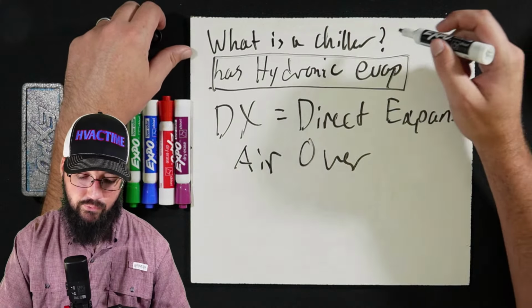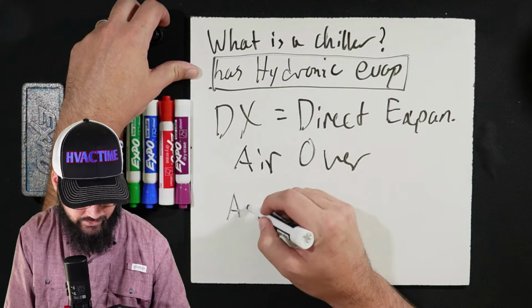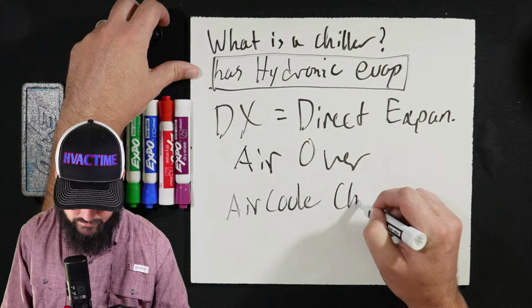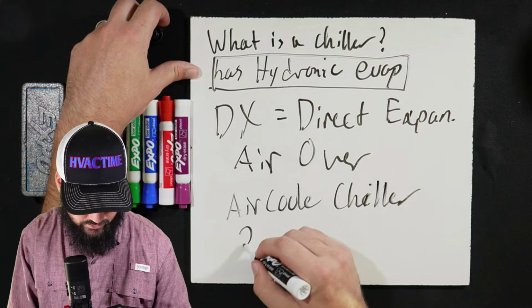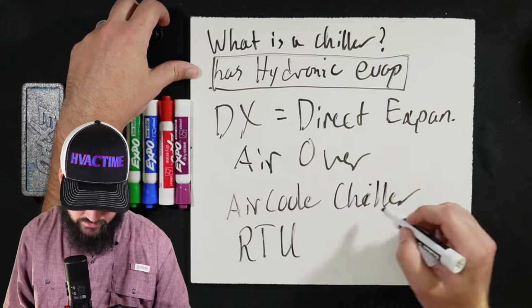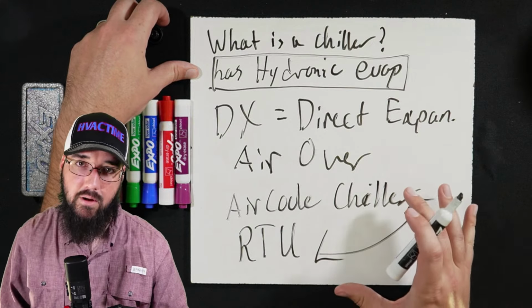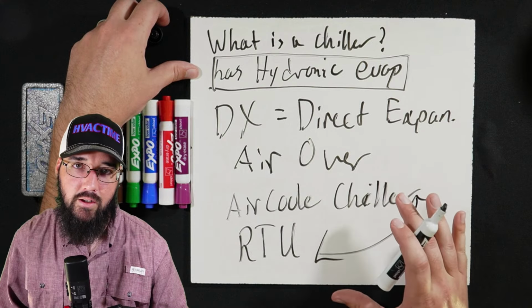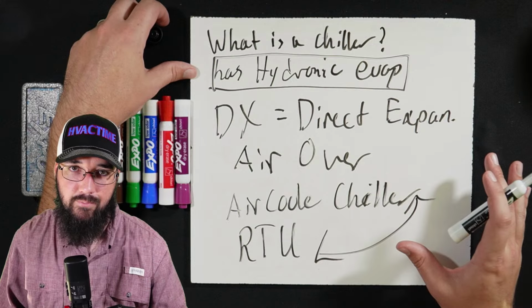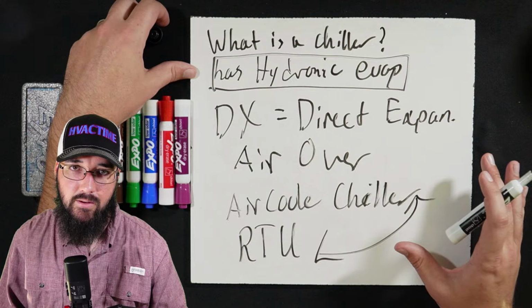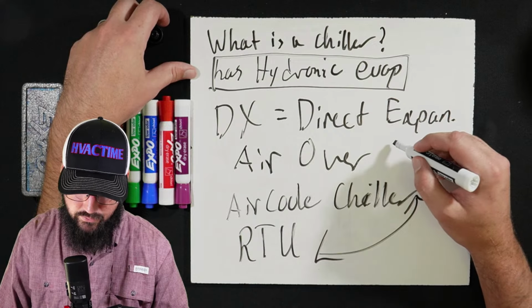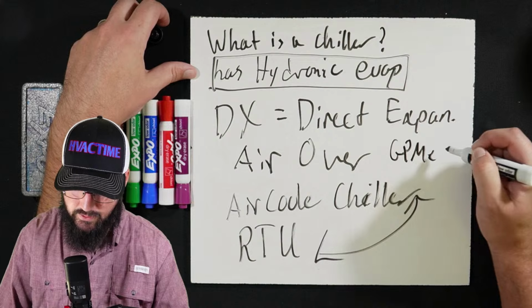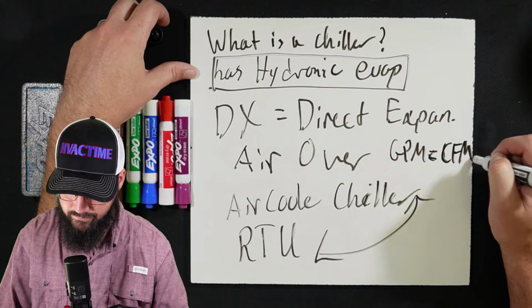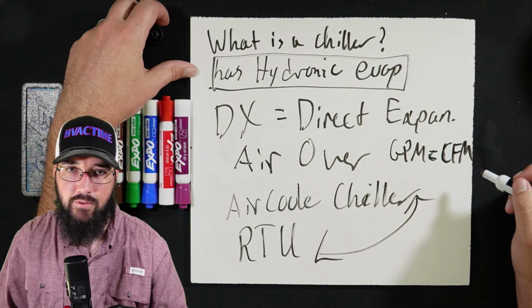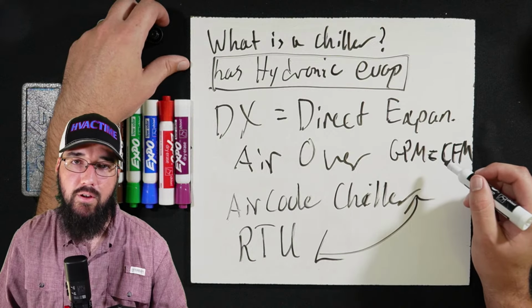And here's a big thing. If you can make the connection between an air-cooled chiller and a RTU, just a standard rooftop unit, if you can make this connection back and forth in your mind, you suddenly understand chillers way more than you think you do. GPM equals CFM. There's the difference. It's just converting one to the other in your mind.